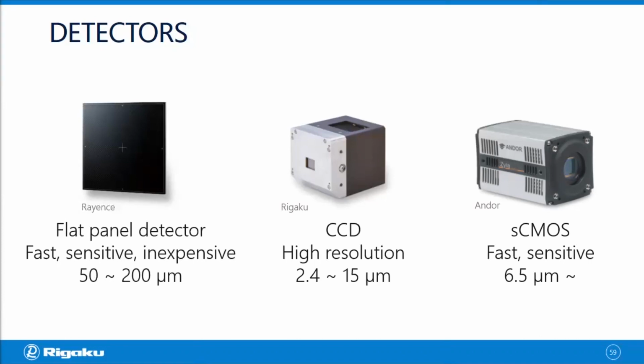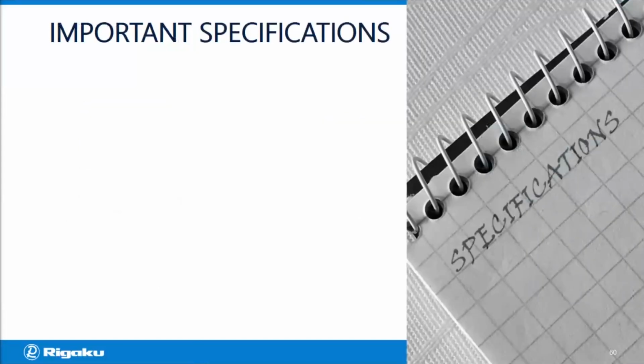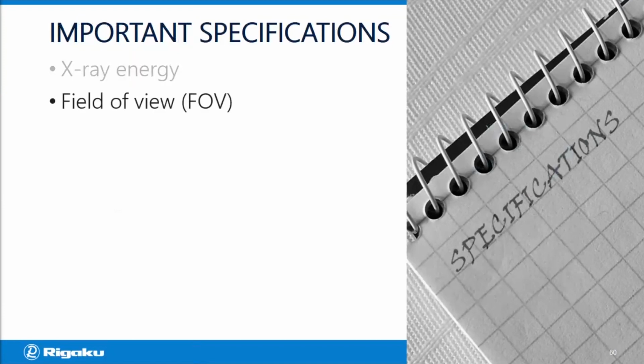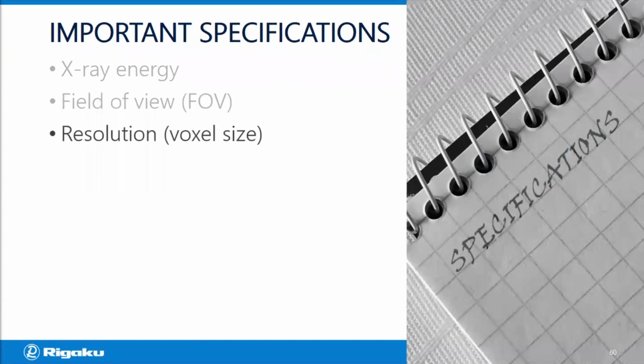So you see that the X-ray generator and the detector are the major components, and they have their own specs, but the specs of the actual CT scanner comes from different parts and different parameters as well. So I would like to go through a list of important specifications. Those are the specs you might want to pay attention to when you're trying to find the right X-ray CT scanner for your research. The important spec number one is X-ray energy. Then you want to look at the field of view, or FOV. That's the area you can scan in one shot. And of course, the resolution. Sometimes people use the term voxel size, which essentially means pixel size in 3D.